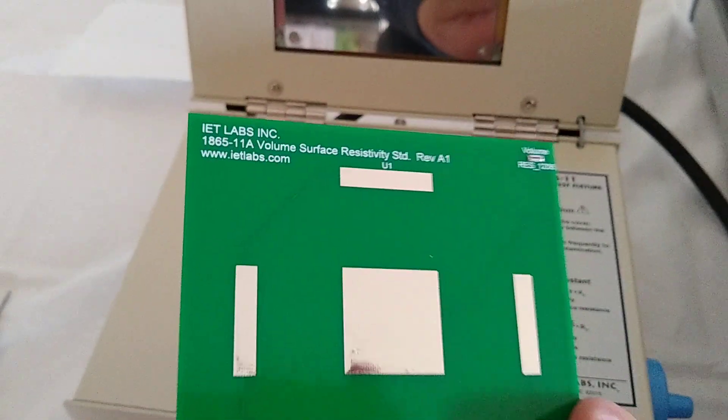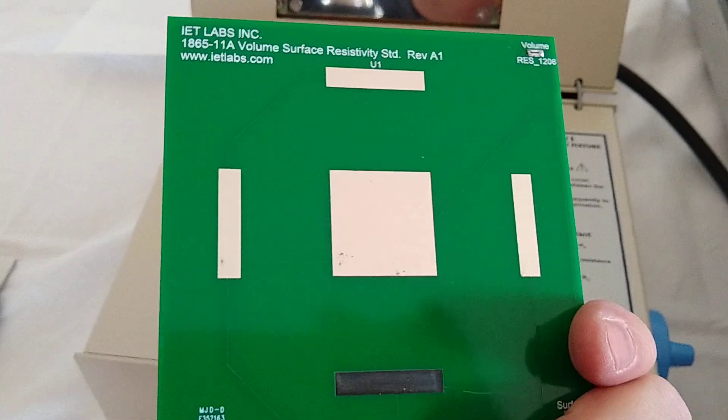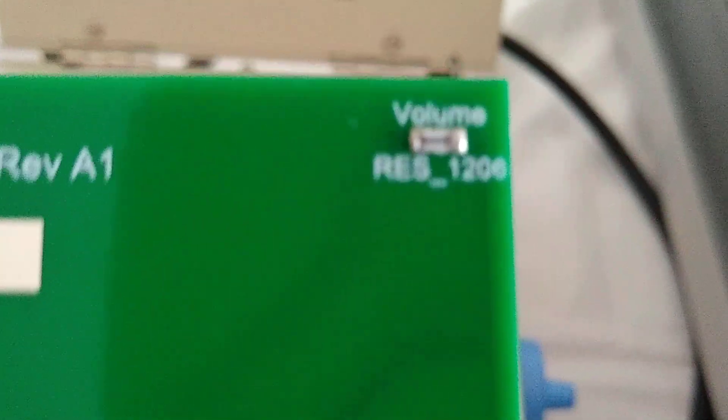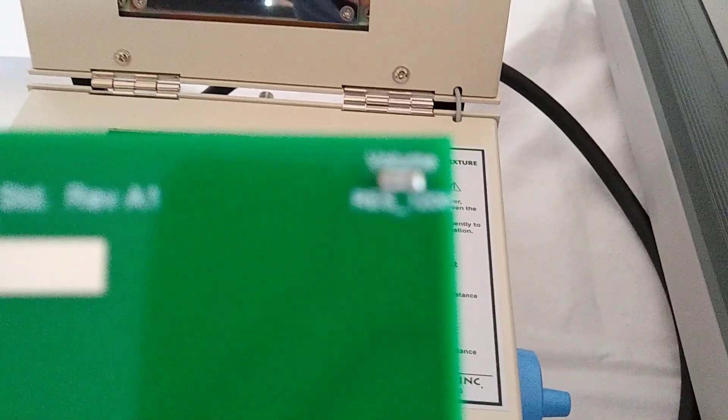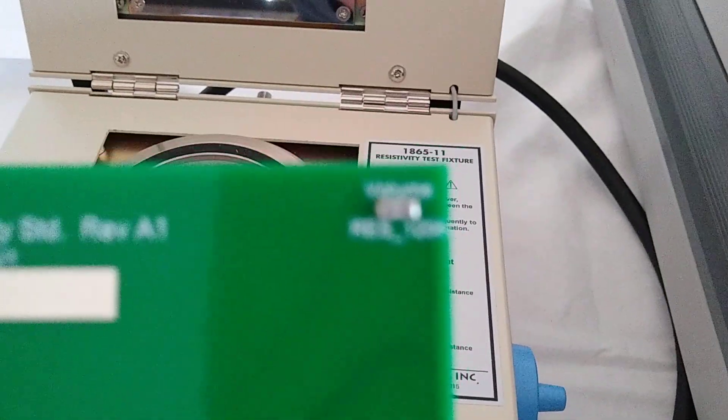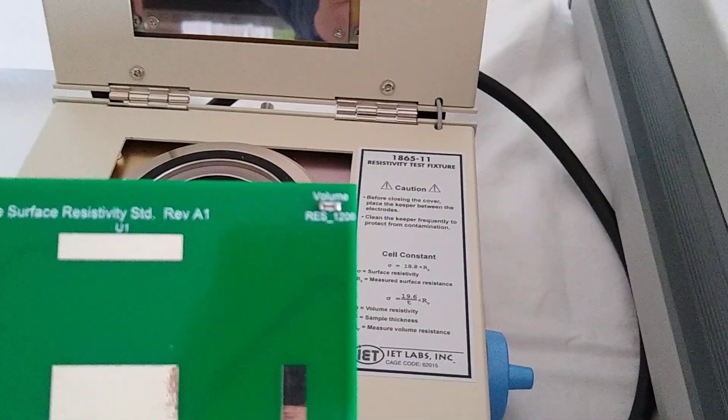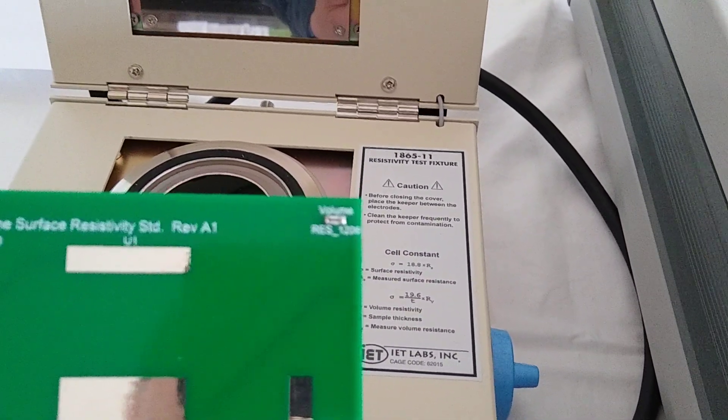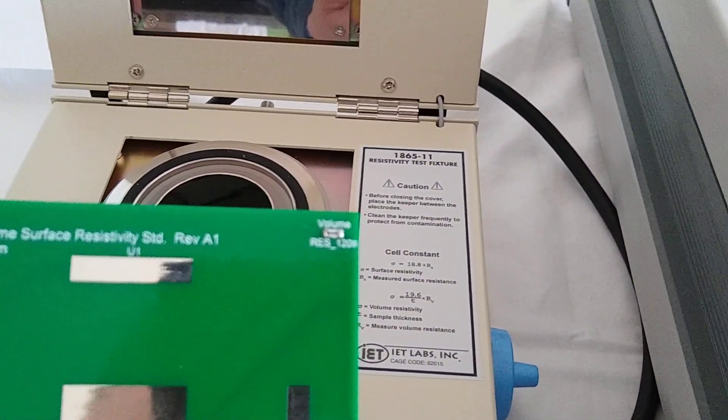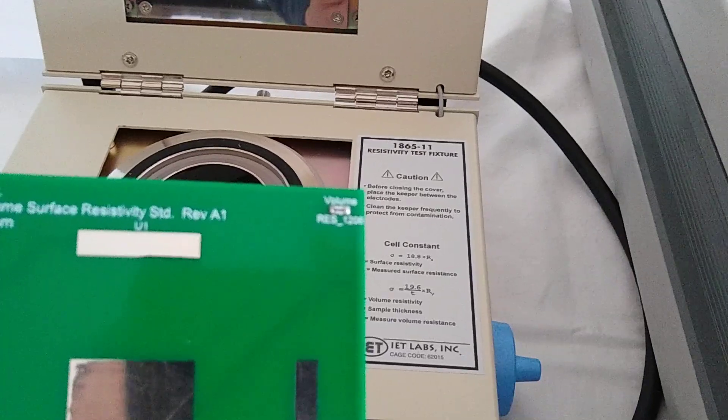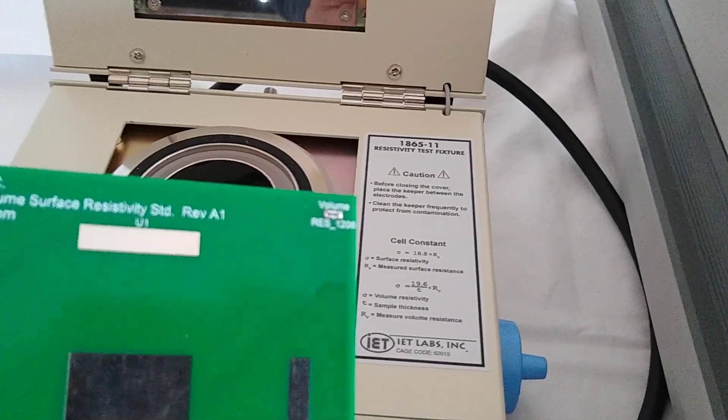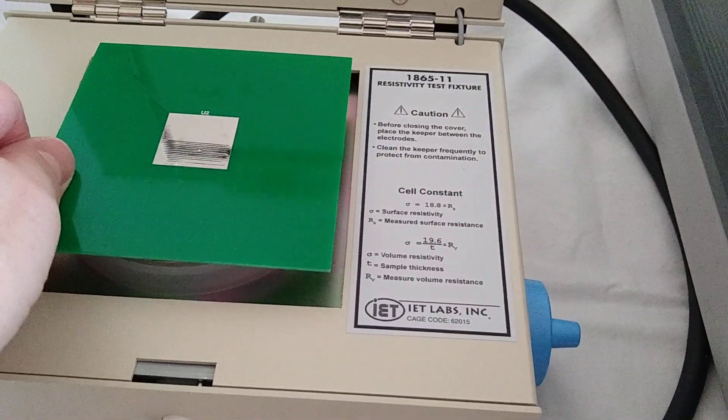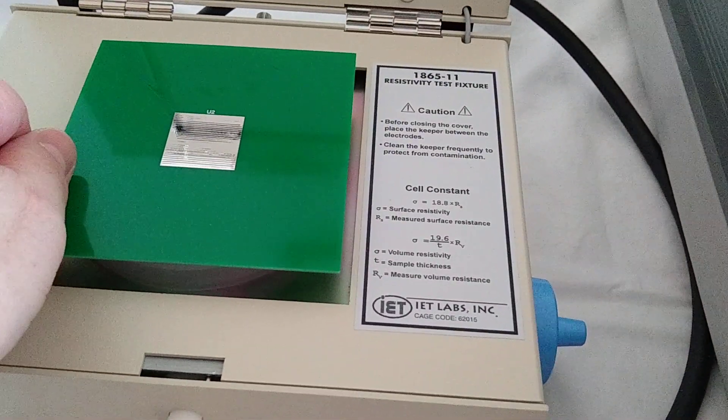We actually use a test sample, which is basically just a PC board in combination with a small resistor. The resistor in this upper corner is just a surface mount resistor. It should give us roughly seven and a half gig for volume resistivity.